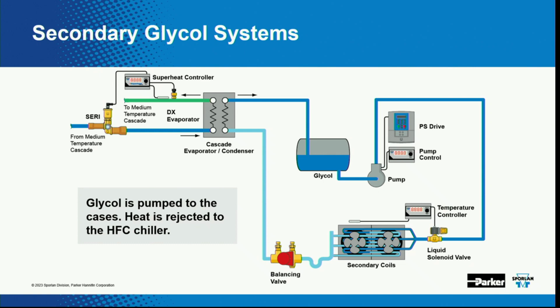All of the HFC, all of the synthetic refrigerant is back at the chiller, and basically what it's doing is cooling this braze plate heat exchanger, or what we call a cascade evaporator condenser. It's an evaporator on the one side, and it's a condenser on the other side. Although again, it's really not condensing because it's already liquid anyway.